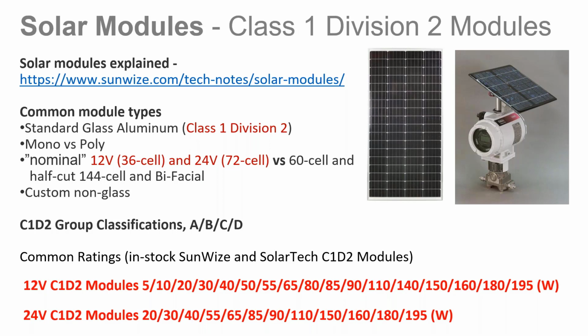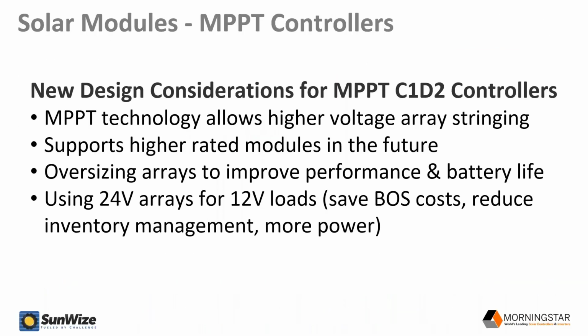You'll see the biggest difference is a little bit less granularity at 24 volt, because nominal 24 volt C1D2 modules are a little bit less common, and they also don't go down quite as small to some of those 5 or 10 watt rating capacities.